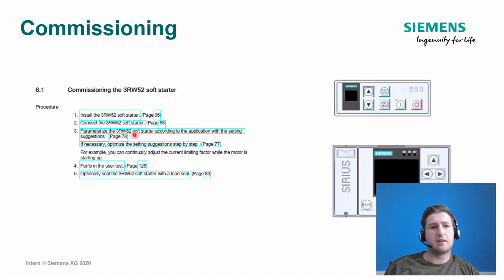So if you get towards the threshold of the current which you've set for the maximum capacity during the startup, the voltage parameter that you've set will be overridden by the current limit function, so it won't go off the time that you've set in the ramp up time. It'll regulate the current until it reaches full speed, by regulating the current instead of using the voltage ramp.